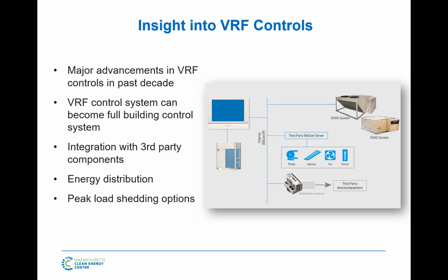And so if you do enable that contact for peak shedding or for load shedding in our software, it's going to tell that condensing unit, hey, if you're only asking for 20% load, you're good to go. But if ever that building starts to ask for 100%, you can't go past 40. That's what it does. So the compressor just won't go past that digitally. That's all internal. That's all done prepackaged by the VRF. You buy that board and you close that contact. I can program the percentage. So that's the people that commission the system, whether it's us as the reps or a contractor that does his own commissioning. You do have to program, but it's just a contact, and then from there, it's all done internally.